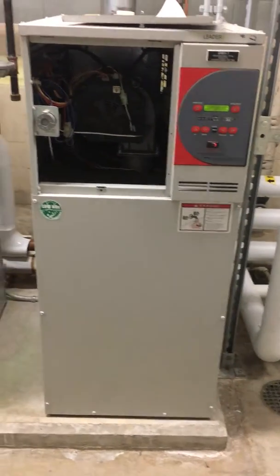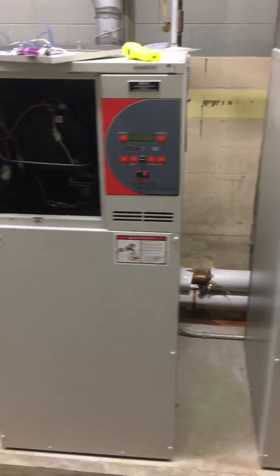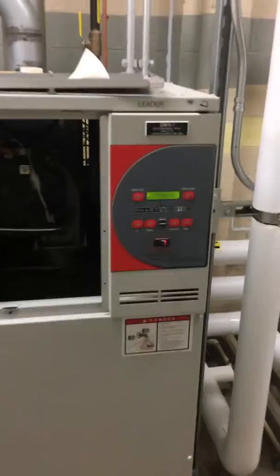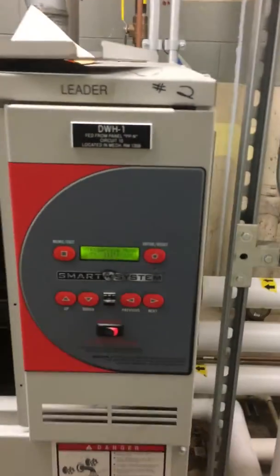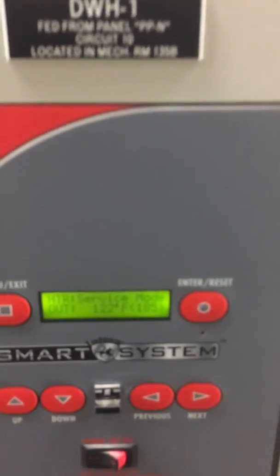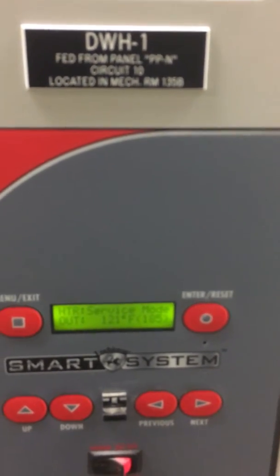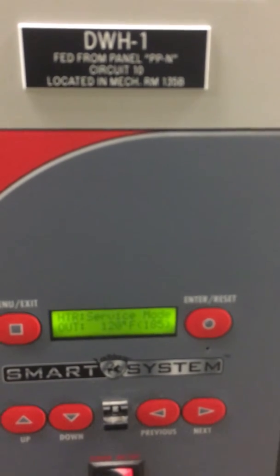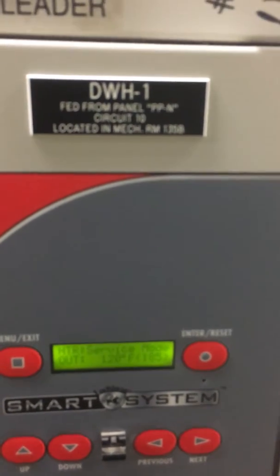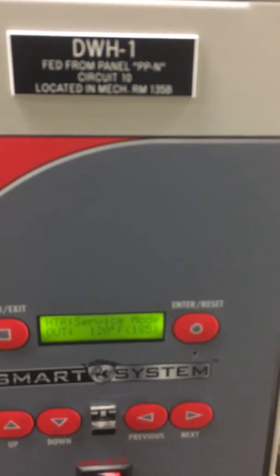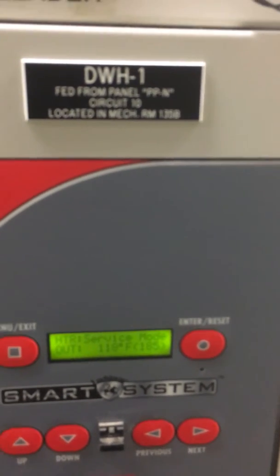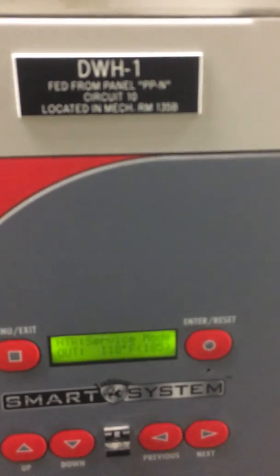Look at it. So, it's at 111, 112. Hear the fan? And it's going up. 115. 116. I'm testing. I'm going to go ahead now. And I'm testing for high gas. So, it should shut down. That was my gas valve, my high gas valve. And I shut it off. So, my Lochinvar heater should actually lock out on high gas. So, it should lock out. Let's look at the indicator.